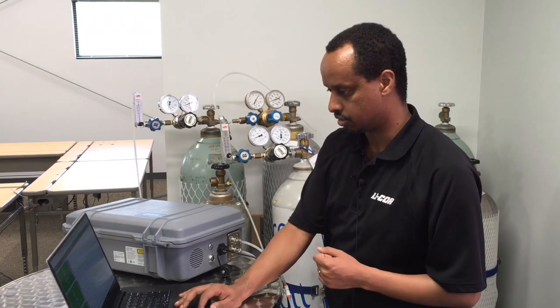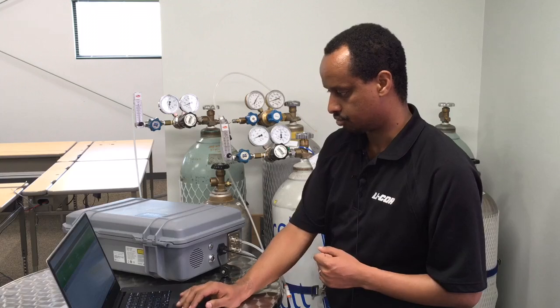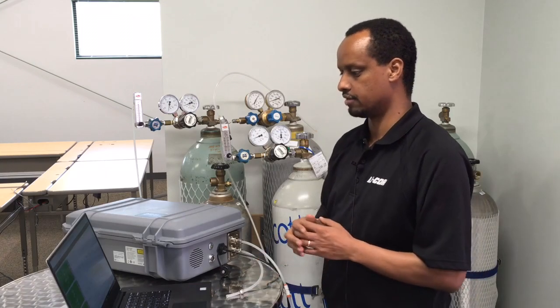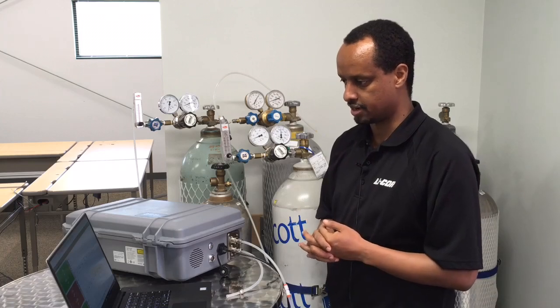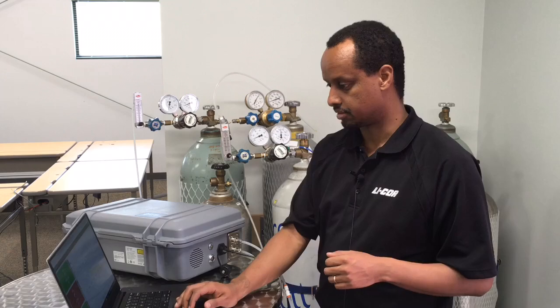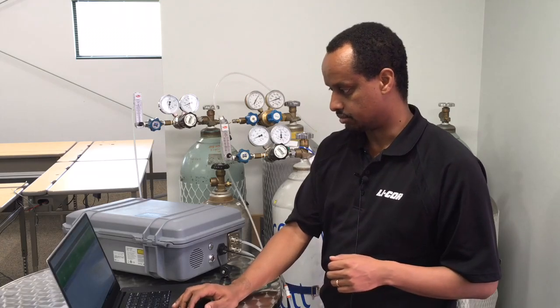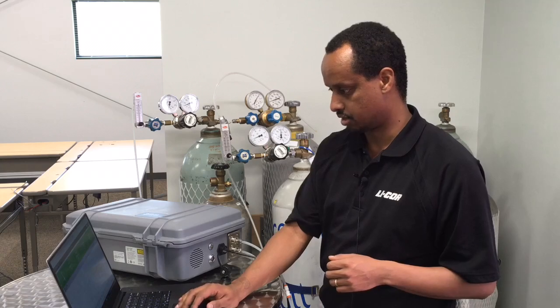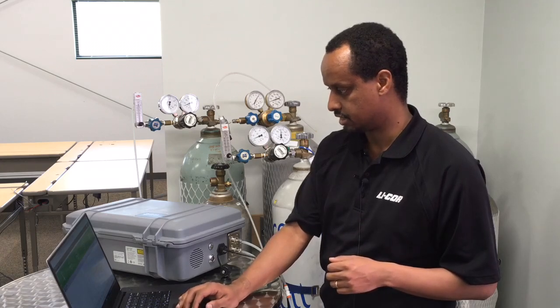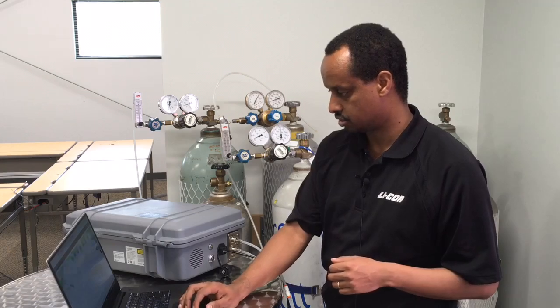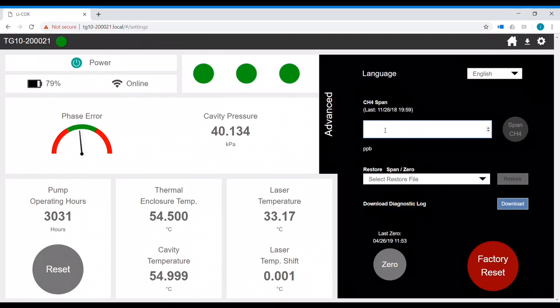As before, we can click on each gas to look at the trend over time. So we'll give it 4 or 5 minutes for things to level out, and then we'll go ahead and do the span. Alright, so it looks like the methane has stabilized quite nicely. There's no movement or change over time, and the mean value we see here has stabilized. So when we're ready to calibrate, again we go to the settings page, go to advanced, and for calibrating the span, we type in the value of the tank in parts per billion. So this tank has 1.99 ppm, which translates to 1990 parts per billion. And once you type in this value, this button gets activated.